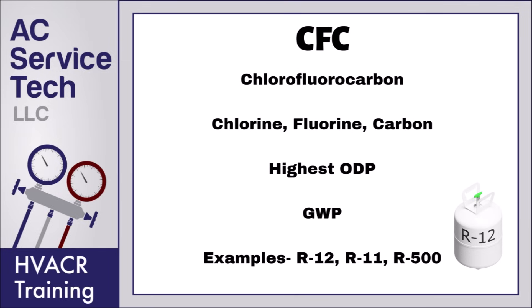CFC refrigerant was one of the first refrigerants developed to have low toxicity. Chlorofluorocarbon was developed around 1928 and went into large-scale commercial use in the 1930s. It's made up of chlorine, fluorine, and carbon, has the highest ozone depletion potential, and also contributes to global warming. Some examples of CFC refrigerant are R12, R11, and R500.